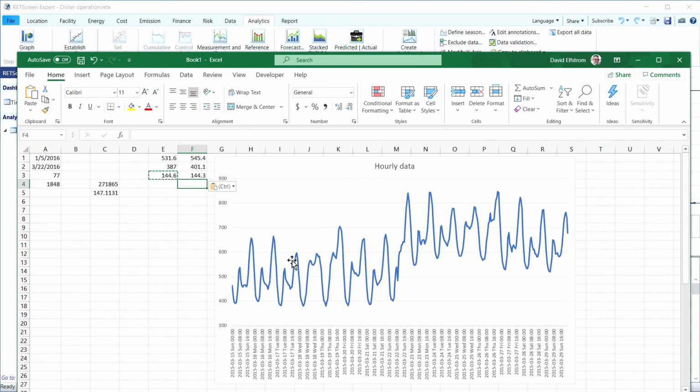no matter what. And the heating still follows with the heating degree days, and then now it's also following with cooling degree days. So there's definitely some simultaneous heating and cooling, which makes me think that there's definitely opportunities for improvement in this building, whatever they may be. And that's a good example of how we can, even without using the hourly data, get really close just by using weekly data and looking at the CUSUM and having a good regression fit.